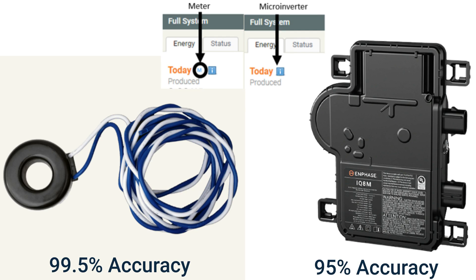It is important to remember that there will always be at least a 4.5% variance due to the accuracy differences between meters and microinverters. Production CT data reports production data at a 99.5% accuracy rate, while microinverters report production data at a 95% accuracy rate.